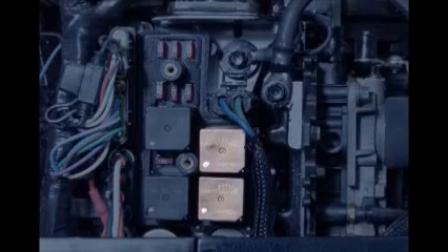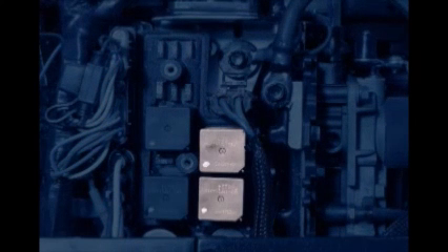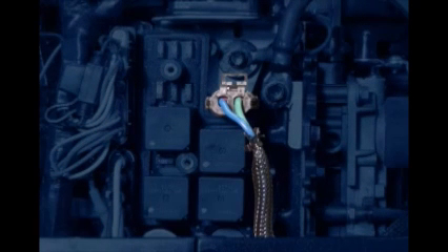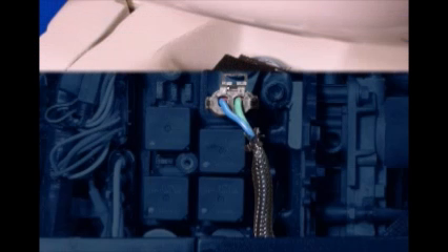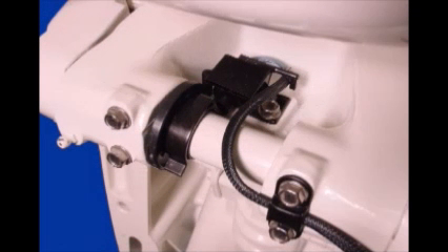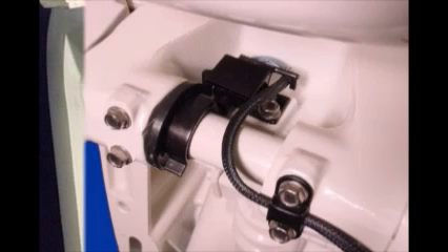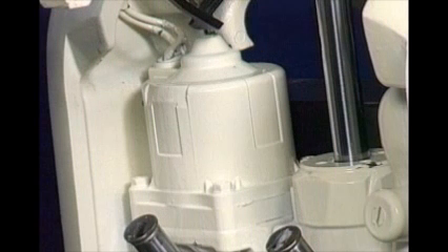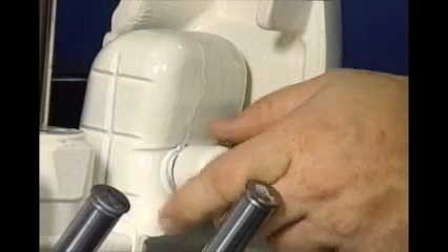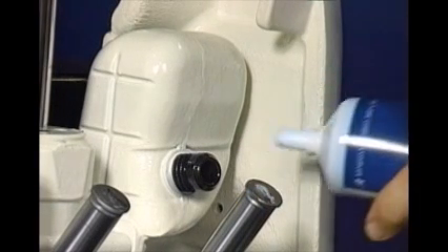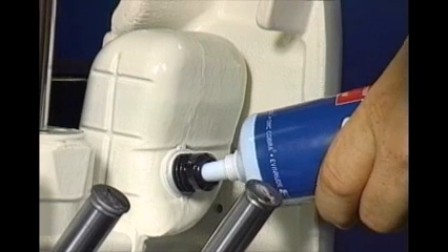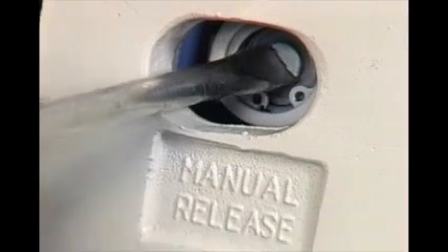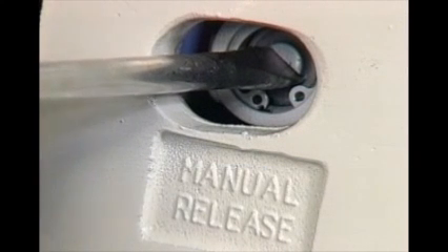Listen for the activation of the relays. Don't overlook the electrical connections. A loose or corroded wire may cause the entire system to malfunction. Check the tilt limiter switch for correct operation. If you can hear the electric motor operating, then the problem is most likely in the hydraulic system. Remember, for the hydraulic system to operate properly, the reservoir must be full of fluid, and the manual release valve must be fully closed.